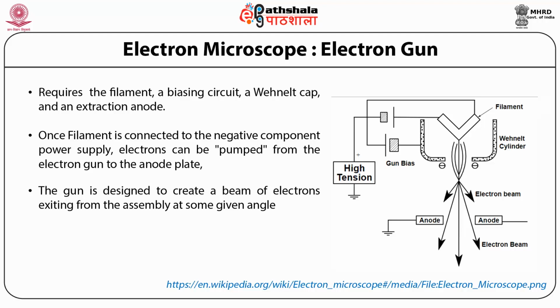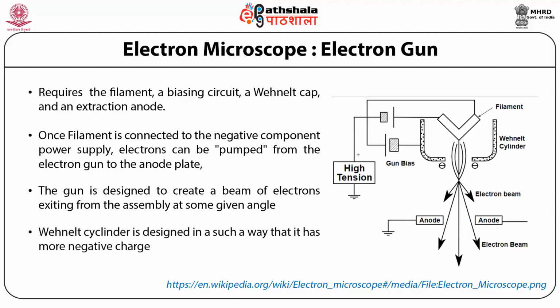The electron beam is directed towards a specific direction. The Wehnelt is designed in such a way that it has more negative charge on it, so that we can focus the electron beam toward the anode directly instead of it getting discharged or spread out within the cylinder.